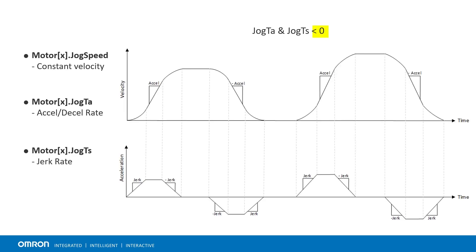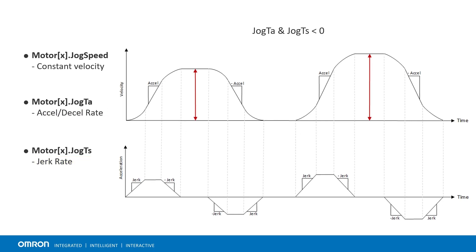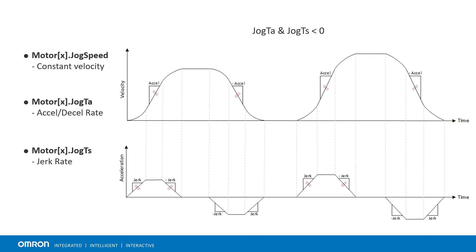...the acceleration and deceleration are defined in rate. Jog TA, in this case, represents the acceleration rate. Jog TS represents the jerk rate. Therefore, at various speeds, the rate of acceleration is constant.